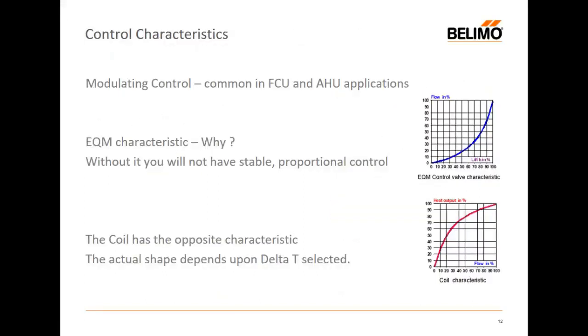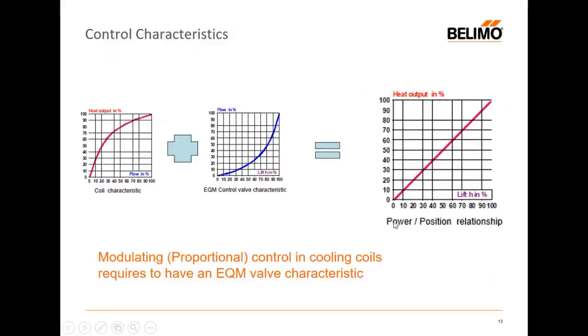So the reason that I need the EQM characteristic is clear. I've got a cooling coil characteristic, which is broadly this shape. And the actual true shape is dependent on the delta. And then the valve should do its best to mirror that image so that when the two are together in the circuit, I've got proportionality in the relationship between the position of the valve, the opening and closing of the valve, and the power output from the cooling coil. So that is where I need my proportionality. That's good quality modulating control, and it's only achieved when I choose a valve which has an EQM characteristic. So very important, if I'm modulating, that I choose an EQM characteristic valve.